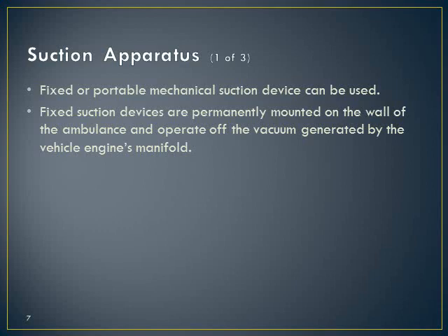So suction apparatuses. Either fixed or portable mechanical suction devices can be used when performing tracheobronchial suctioning. As we know, the fixed suction units are permanently mounted on the wall of the ambulance and operate off a vacuum generated by the vehicle's engine manifold. These are what would be preferred to use, because again, you have the ability to dial in more exact pressure than using one of the portable suction devices, which oftentimes just have one setting, which is a medium-high setting typically. Fixed suction devices should be capable of usually having 40 liters per minute and a vacuum of at least 300 millimeters of mercury when the suction tubing is occluded. The portable mechanical suction device, whether powered by oxygen, air, or battery, usually does about 20 liters per minute, which is usually effective for us.